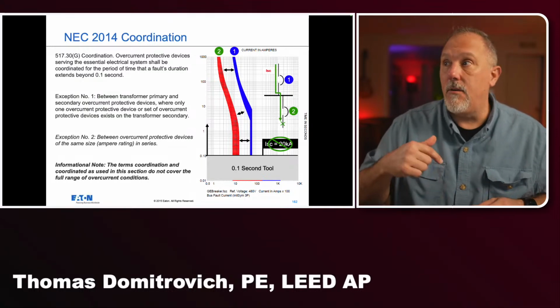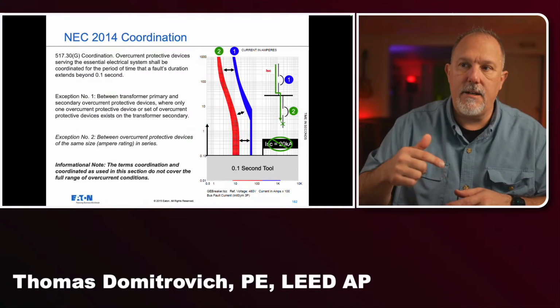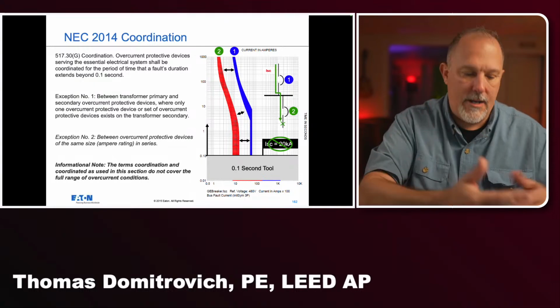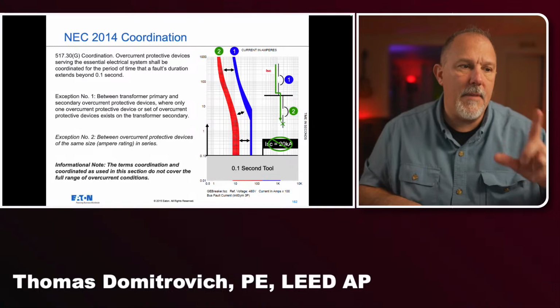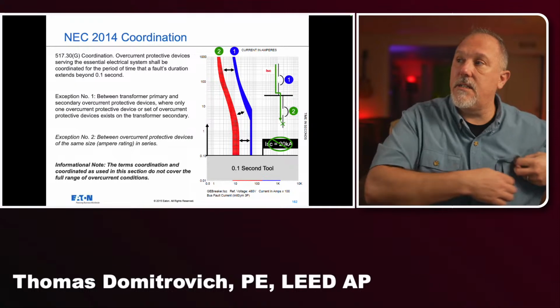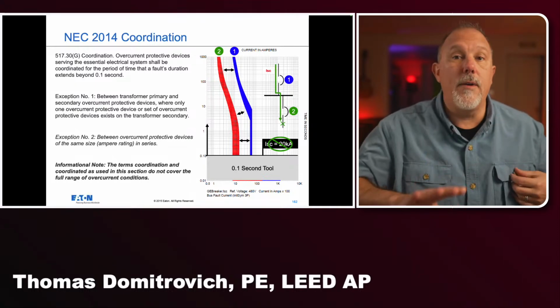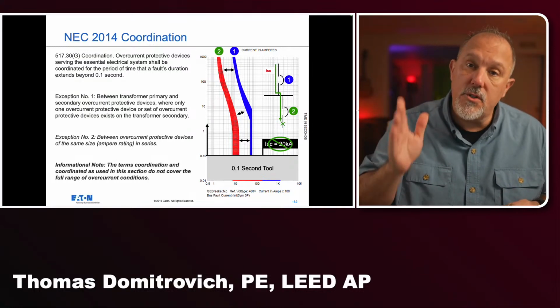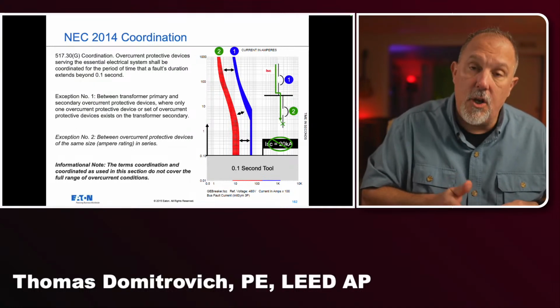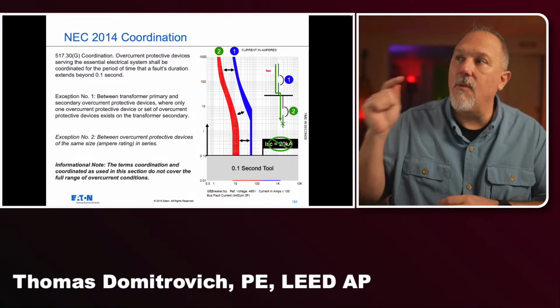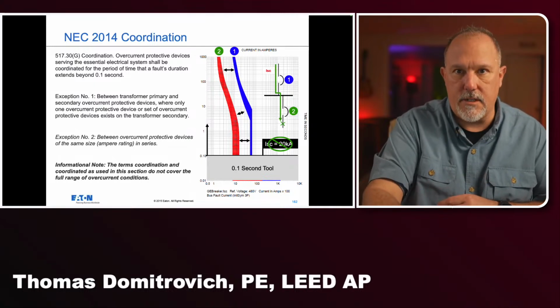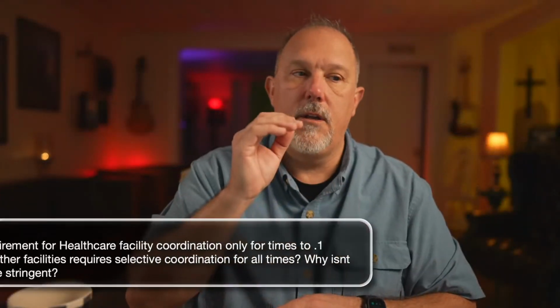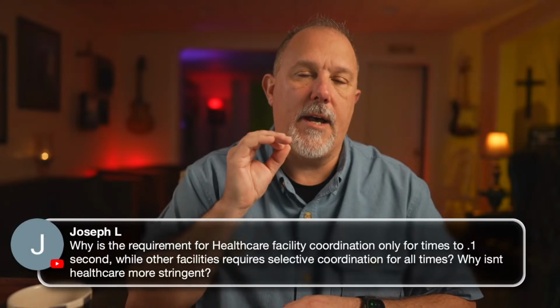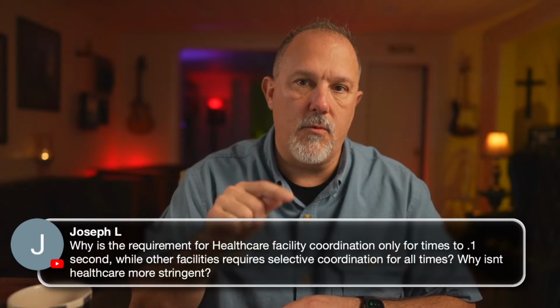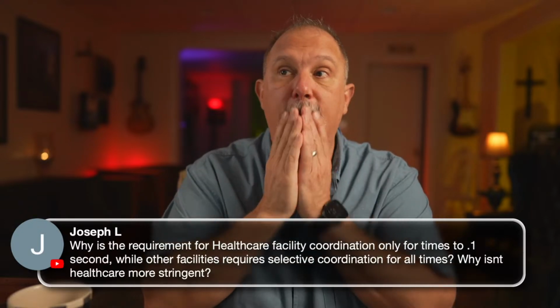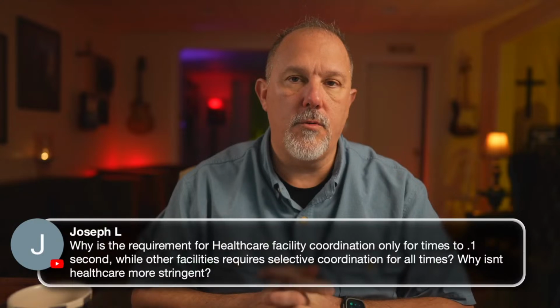Now, as an engineer, let me tell you a scenario. I was talking to somebody who was on NFPA 99 and panel 15, and I made the statement, we were having this debate, and my biggest issue with 0.1 seconds is ignoring fault current. Ignoring any current. I don't even compare the most common fault current in a power distribution system, which is ground fault current. I don't even look at whether or not a ground fault current will cause a cascading event in a healthcare system. All I care about is whether or not an overload takes out more than one circuit. And I would probably argue in a lot of those healthcare scenarios, your chances of an overload, you're controlling your circuits so much.